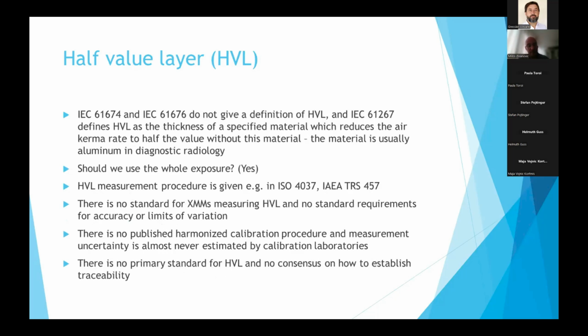And again, if you look at IEC 61674 and IEC 61676, there is no definition for half value layer. There is only a simple definition in IEC 61267. It says that HVL is the thickness of a specified material which reduces the air kerma rate to half of the initial value. And this specified material in diagnostic radiology is usually aluminum. So we usually specify HVL in millimeters aluminum.